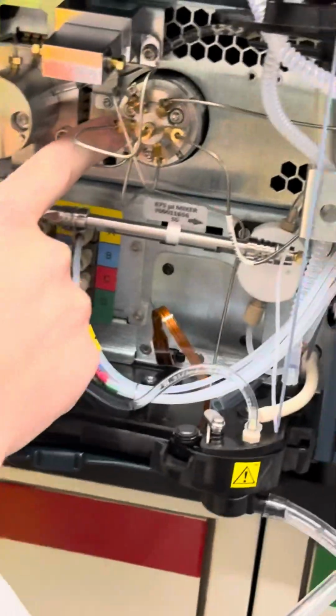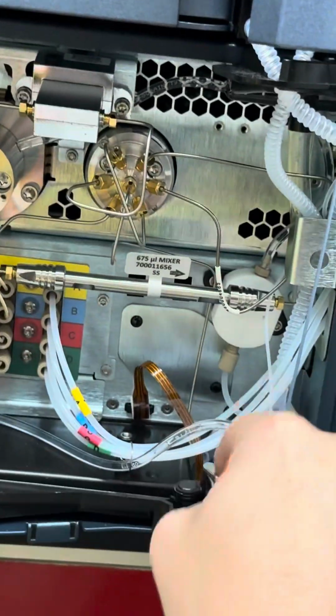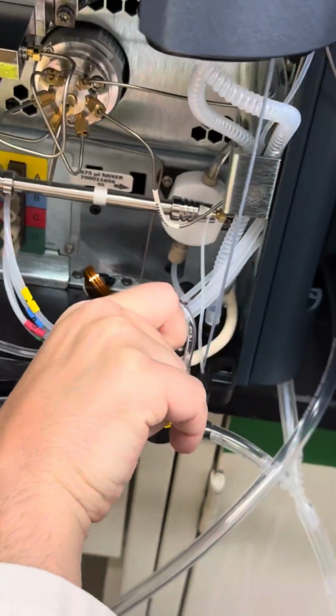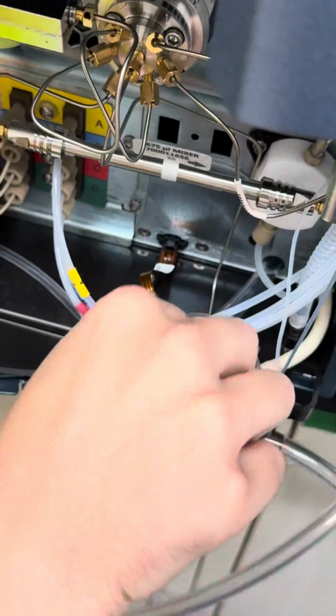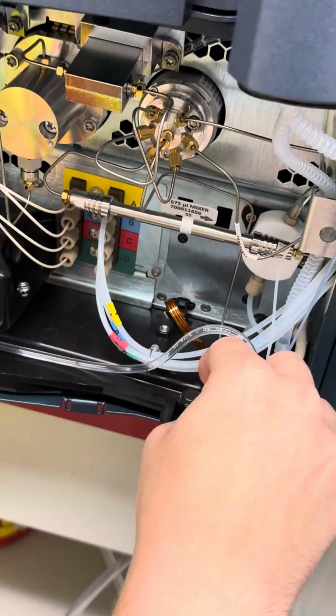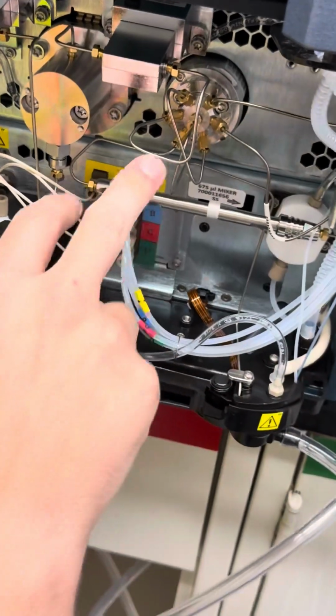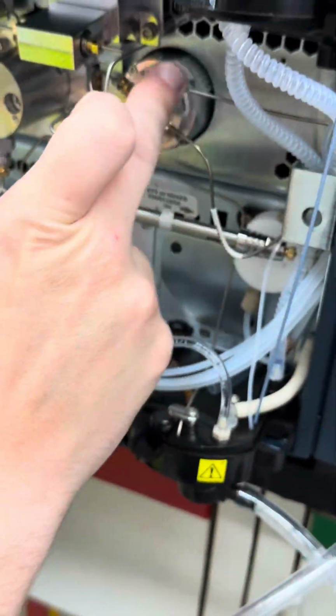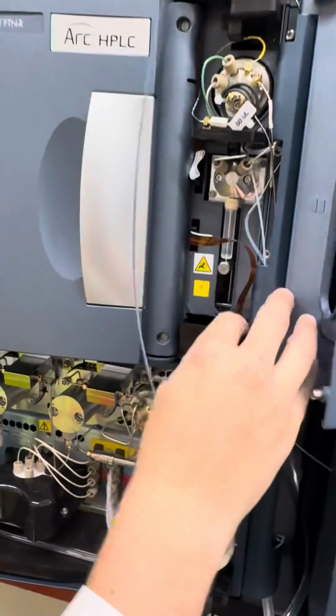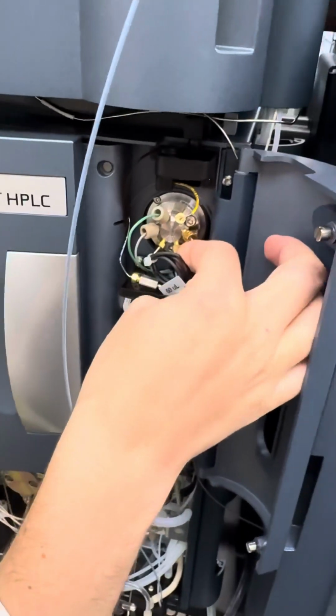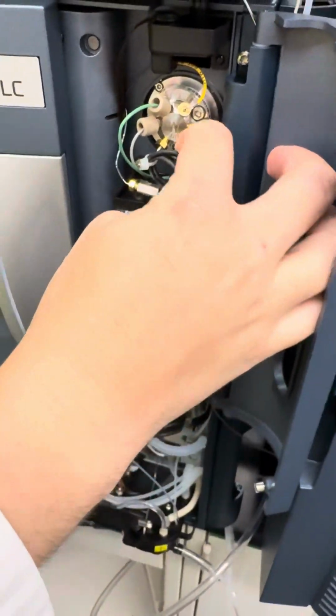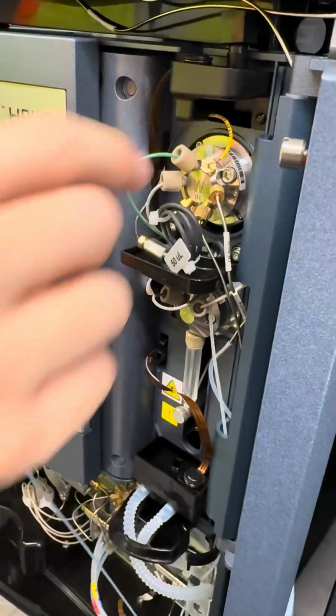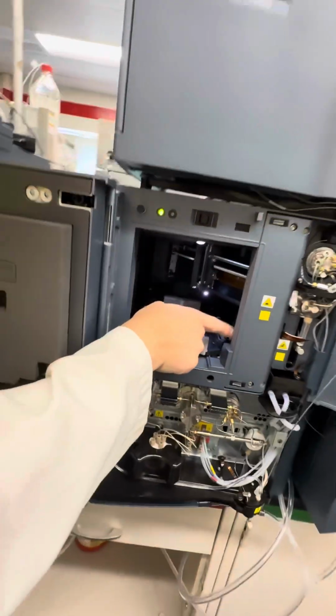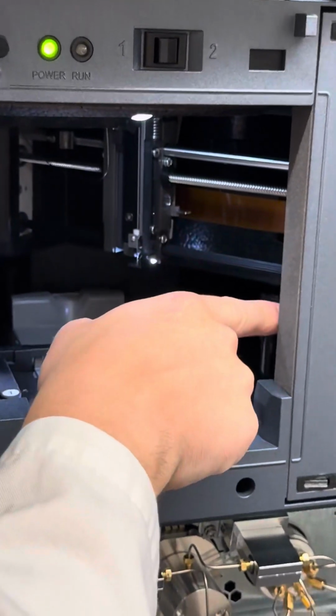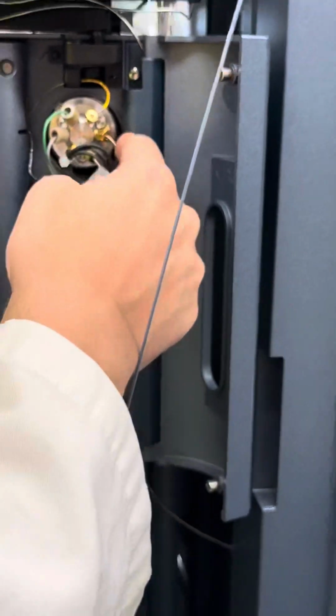Now, when you prime it, as we were before, it drops and it goes down here. So you can actually, if we prime it, you can check and see if it's actually flowing out of here. So we can do that in a little bit. Now that I got that out, put that back in and we'll put that over. Otherwise, it's gonna go through your path 1 mixer and then out and up. And it'll flow up here into this spot right here. All right, and since it's a flow through needle, it's gonna go through your needle, back around. It'll go through your needle. There's like a little wash housing here. So it goes through your needle, through your wash housing, up here, and then down to your column.